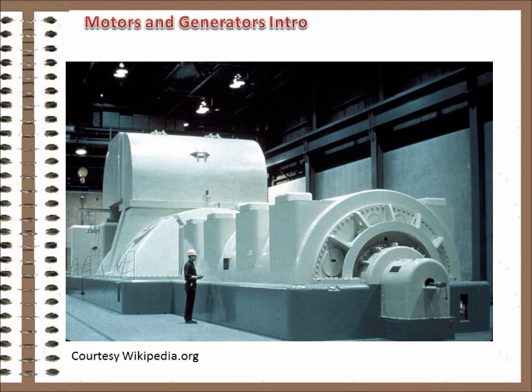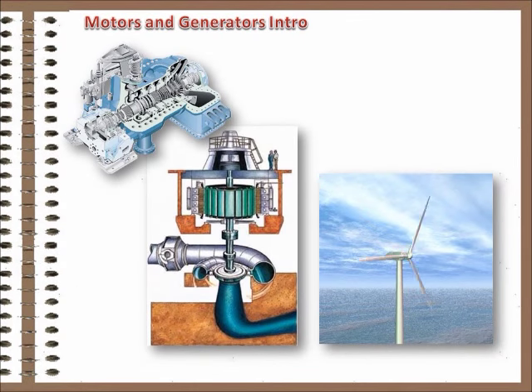Now, let's turn our attention to generators, specifically three-phase synchronous generators, or alternators as they are technically called, the kind of generators most commonly used in power systems. They are very similar to synchronous motors, minus the winding tricks motors use to get up to speed, because generators are driven up to speed by a prime mover, a steam, water, or wind turbine.